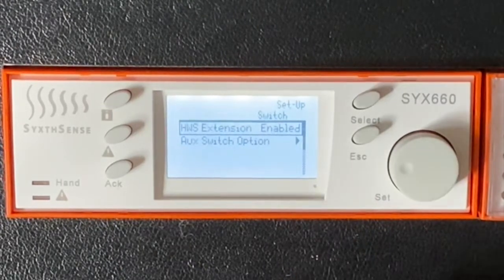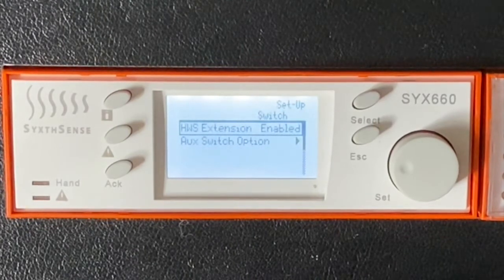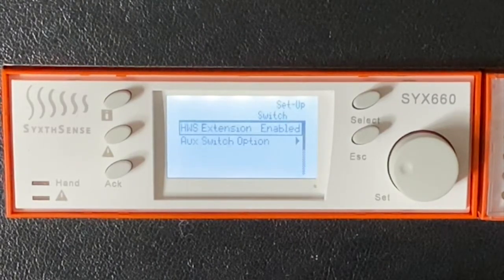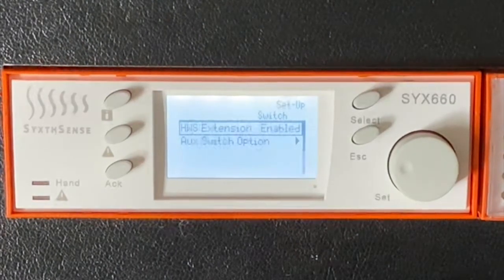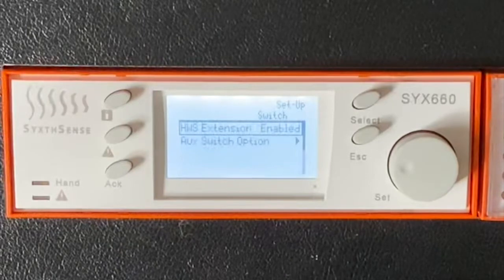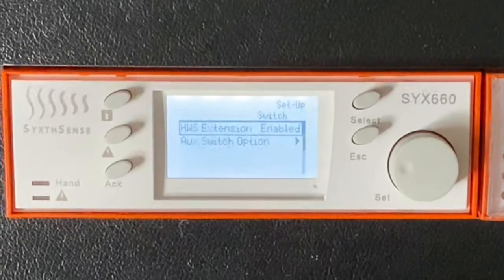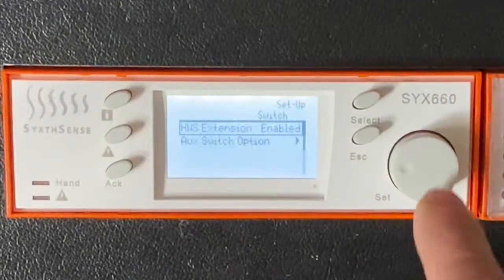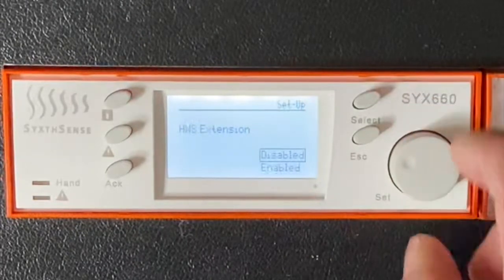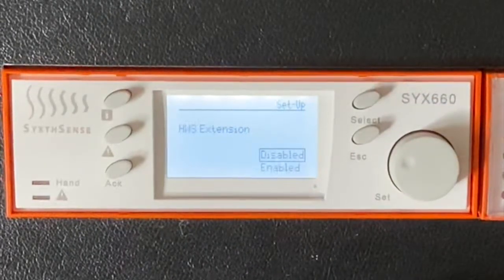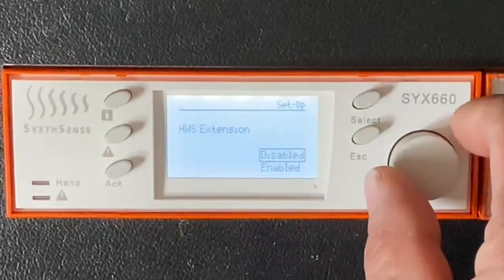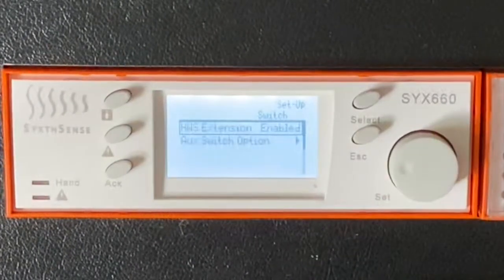Here are the 2 options that we have to choose. The first option is hot water extension feature. Do we want the hot water to be overridden into day mode when the heating day mode override switch has been activated? We can choose enabled as default, or we can press the wheel and choose disabled if we do not want the hot water to follow that override. We're going to leave that set as enabled.